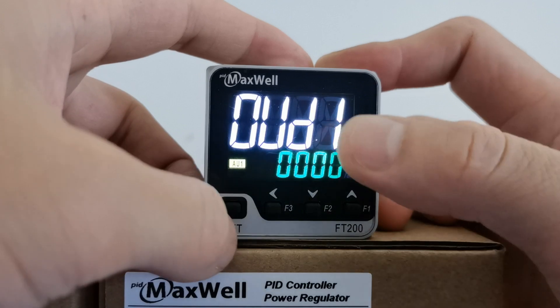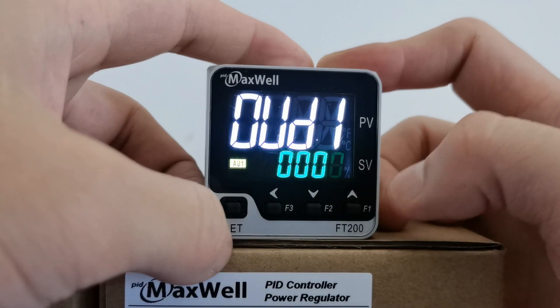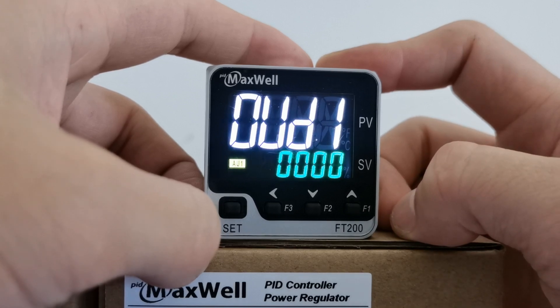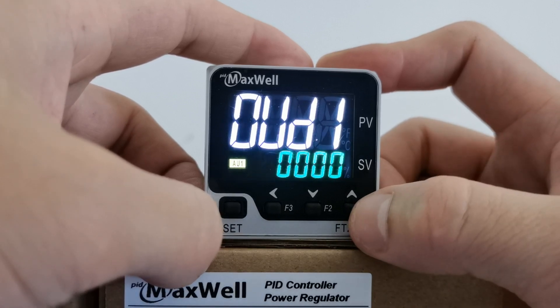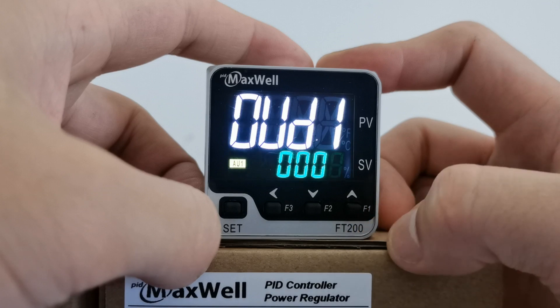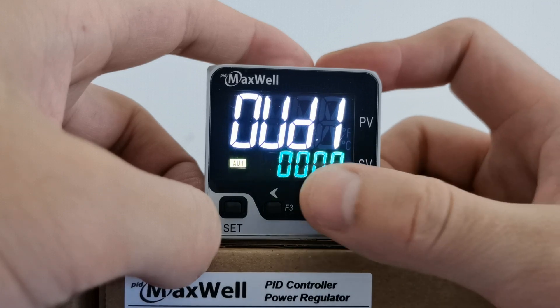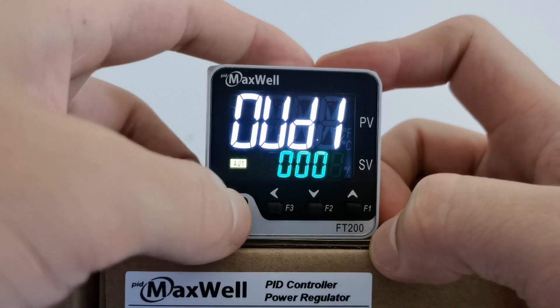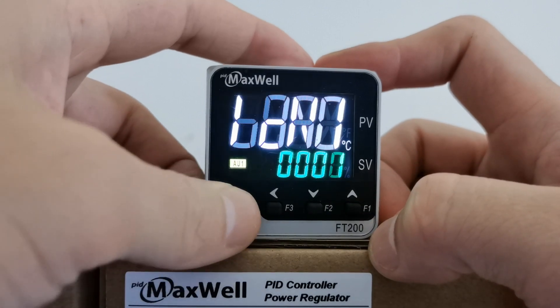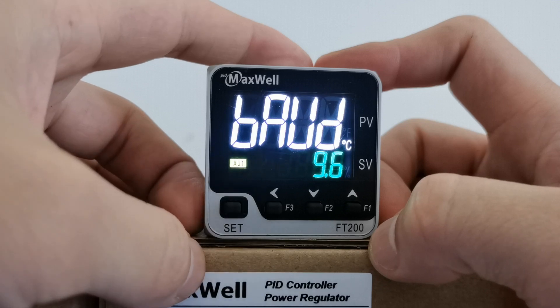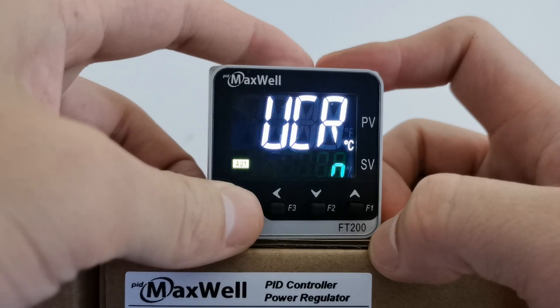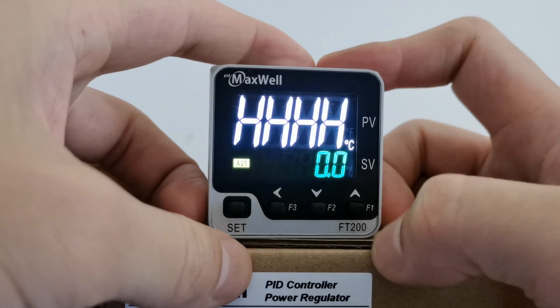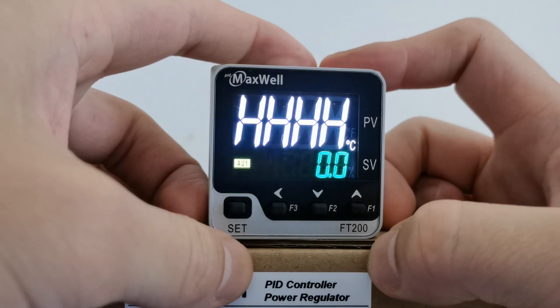To configure the control mode: the factory default control mode is heating mode. In this case, if you need cooling mode, change the value from zero to 0001 and you're good to go. Press the set button to save the configuration.